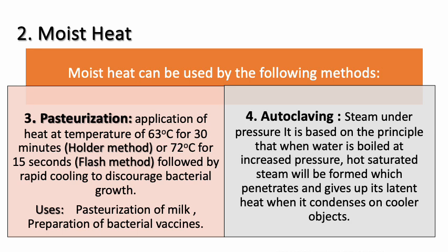The next one under moist heat is autoclaving. This is one of the most effective methods of sterilization, and it is commonly used in the microbiology laboratory. The principle is that it uses steam under pressure. When water is boiled at increased pressure, hot saturated steam is formed, which penetrates and gives up its latent heat when it condenses on cooler objects, thus killing the bacteria inside out.